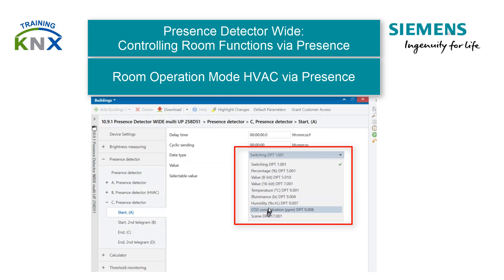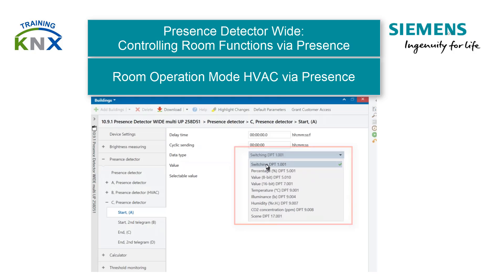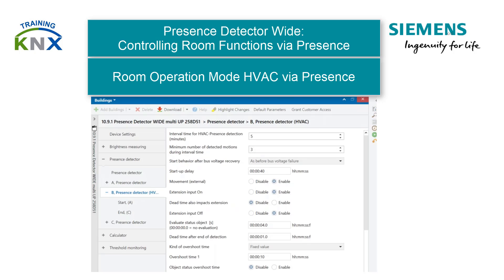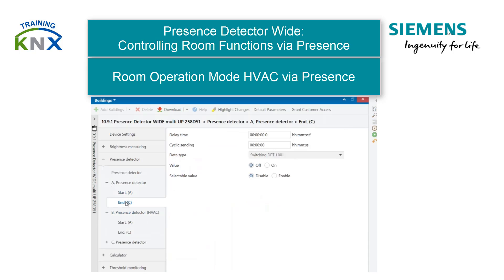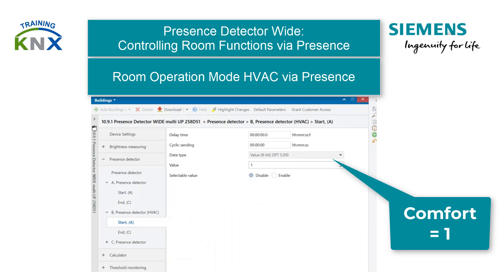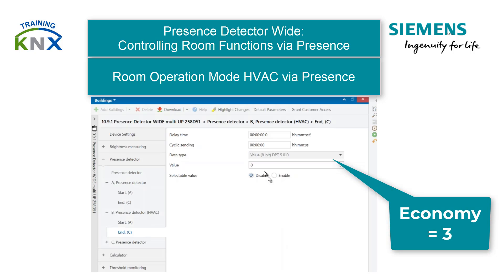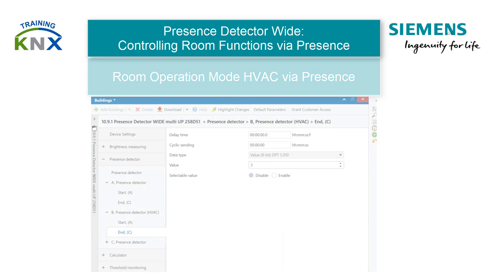An example is the Presence Dependent Room Operation mode. With Function Block A, the light is switched depending on brightness. With Function Block B as Presence Detector HVAC, the temperature control is switched between economy and comfort independent of brightness. Please note that you have to set the values 1 for comfort and 3 for economy in data point type 5.010, because there is no DPT-20102 room operating mode.